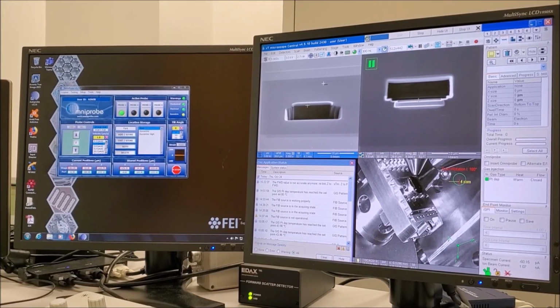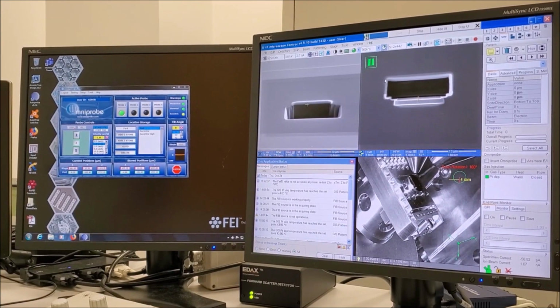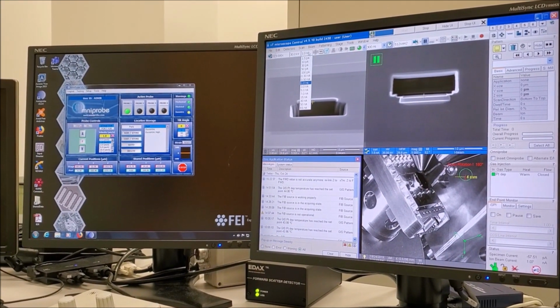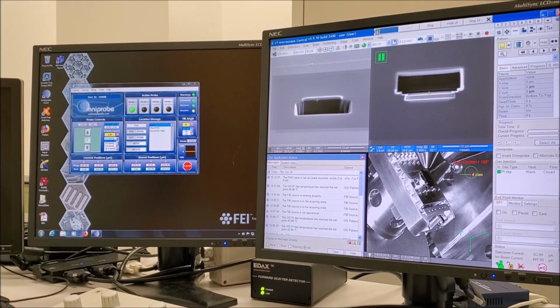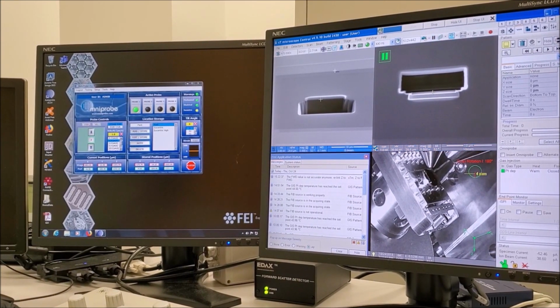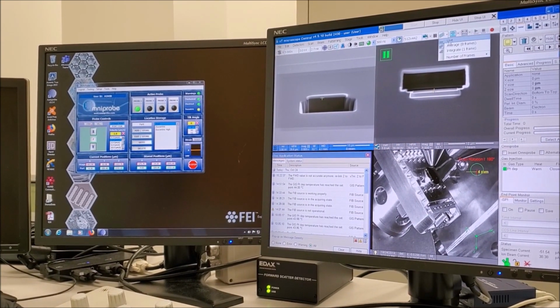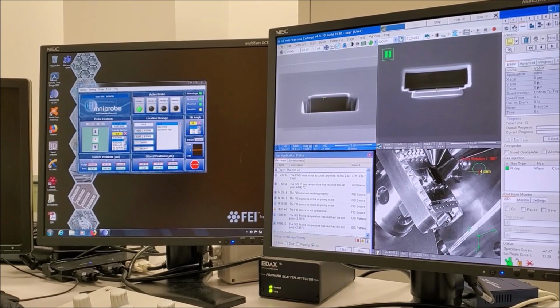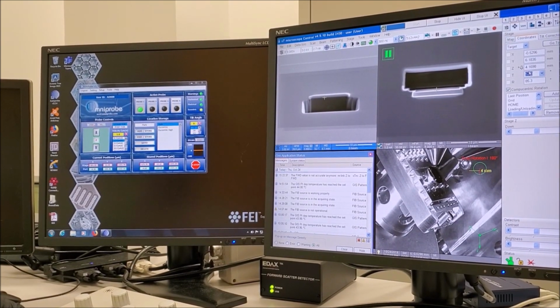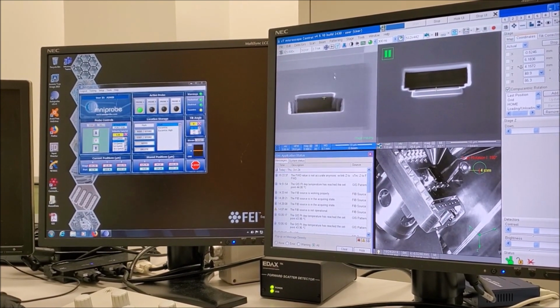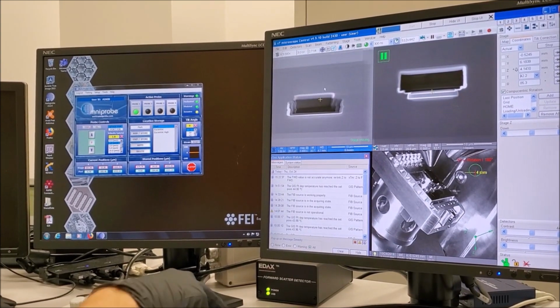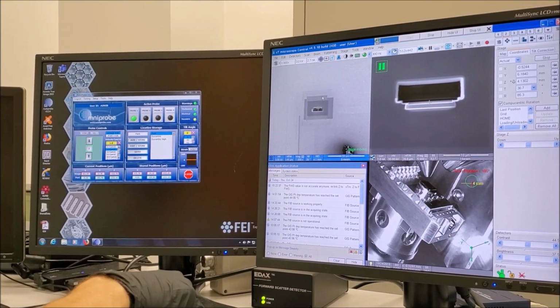When using the OmniProbe, it is important to keep in mind that it should only ever be inserted and manipulated with the sample at eucentric height and the stage tilt at or very close to 0 degrees. Activate the electron beam quad and unpause to acquire a live image. If the stage is not at 0 degrees, enter the navigation module and tilt back to 0 degrees.